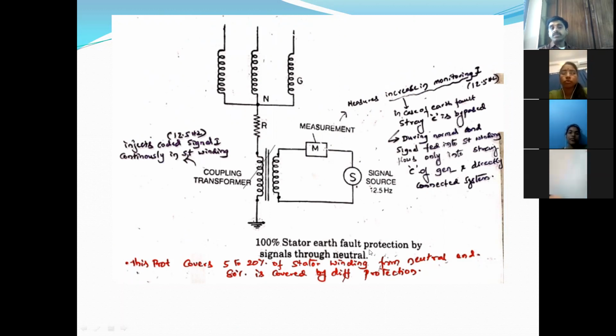100% stator earth fault protection by signal injection through the neutral. What we are doing here is using a signal source of 12.5 hertz. That means a low frequency signal, one fourth of 50 hertz. That is injected through a coupling transformer, through the resistance, from ground to neutral. So it injects a coded 12.5 hertz signal current continuously in the stator winding. Percentage differential protection is already there, which provides 80 to 85% protection. How will the remaining 15 to 20% be protected using this scheme?